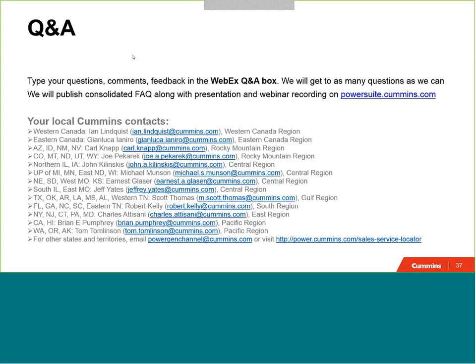All right, next question, Mike. Thank you. Can you describe the cons and pros of 2HR versus 4HR full load testing? Yeah, the question's about 2-hour versus 4-hour full load testing, and realistically, especially if we're talking about site testing or even factory testing, most generator sets, when installed on site, if there are going to be any issues with the commissioning process or the initial installation operation, it's going to be caught within, I'd say, the first 2 to 4 hours of operation of the product.